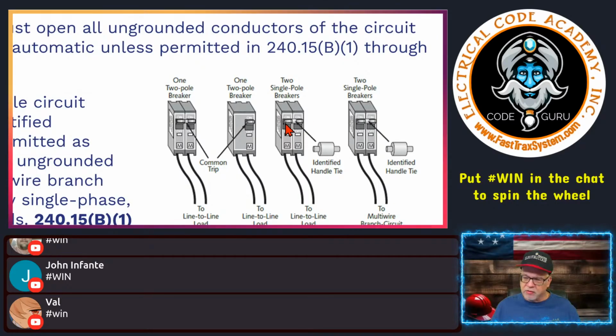That's like 240-volt loads. But then also you can have two single pole breakers with identified handle tie between them, and it can handle line to neutral loads for a multi-wire branch circuit. Again, y'all are probably way familiar with this. Now, y'all know the reason why in a multi-wire branch circuit it's so important to either use a two-pole breaker or, if you choose to use two single poles, an identified handle tie. It ensures that when the breakers are installed they're on opposite legs, because it alternates down the panel board. So this allows for the neutral to carry only the maximum imbalanced loads.